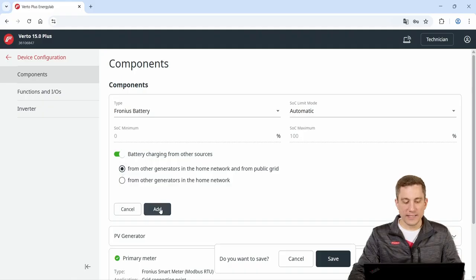When you have done all the settings, you can hit the Add button and please, very important, the Save button to make sure that the new settings are applied and the hybrid system is now commissioned. Please also note that you can now log into your Solar.web system and make a firmware update for the battery system online. So whenever you want to do a firmware update of the battery system, you can do this directly over the Solar.web system from afar. There is no need to go to the customer site in person.